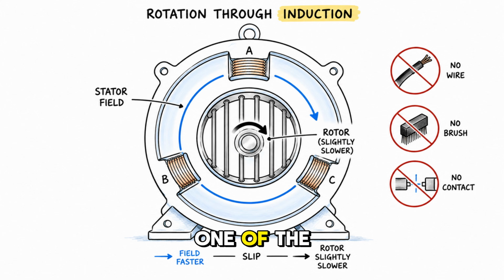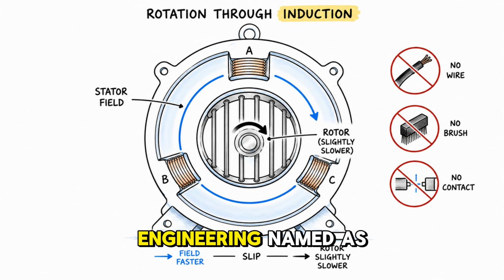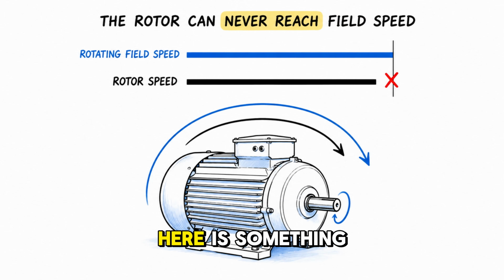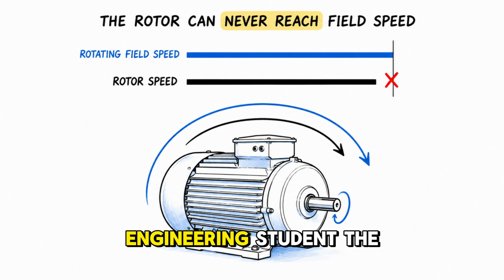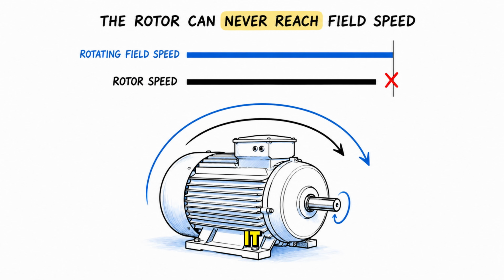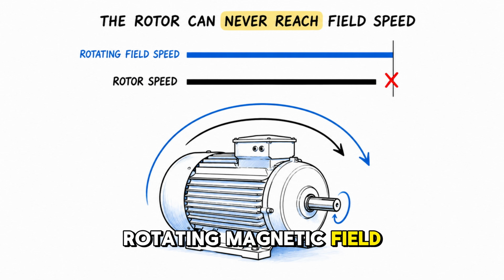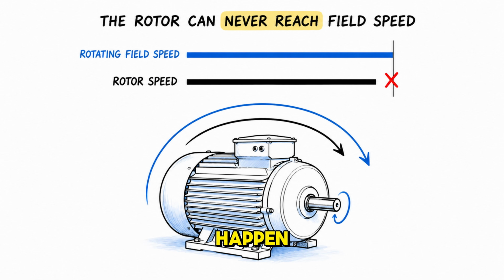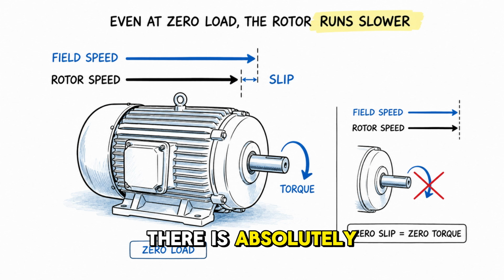And this brings us to one of the most important concepts in motor engineering, named slip. Here is something that surprises almost every engineering student the first time they hear it. An induction motor can never reach the speed of its own rotating magnetic field. It can never happen. Not even when there is absolutely zero load on the shaft. It always runs slightly slower. This speed difference is called slip. And without slip, the motor produces zero torque and stops working entirely.